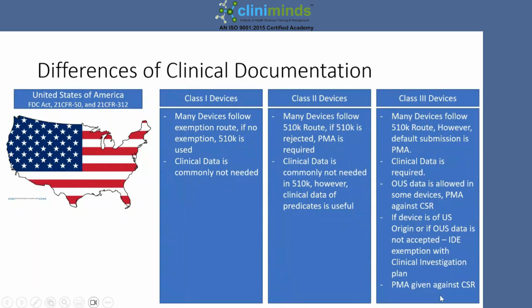Third is the pre-market approval, or pre-market application. These devices need to have a lot of documentation, which includes clinical data. Outside-US clinical data in certain devices may be allowed, but in many devices it may not be allowed. In that case, I may have to go with an investigational device exemption, conduct a clinical investigation in the US and submit that report. When that report is submitted, I get the permission to sell. So this is the difference between Class 1, 2 and 3 devices in the US.